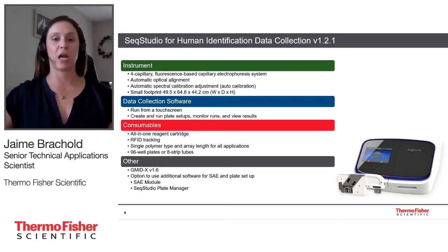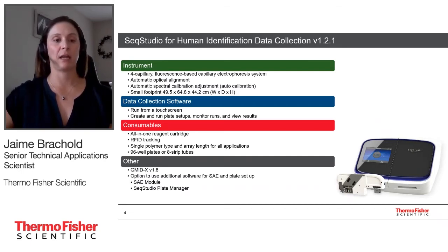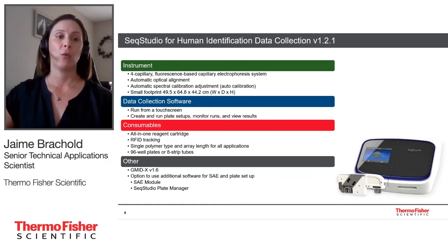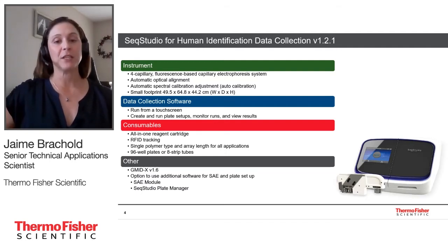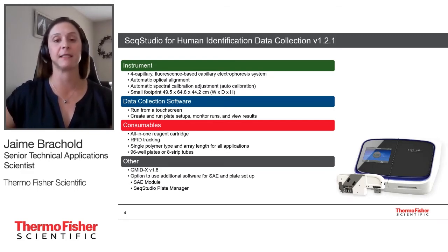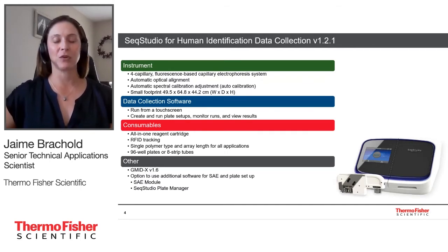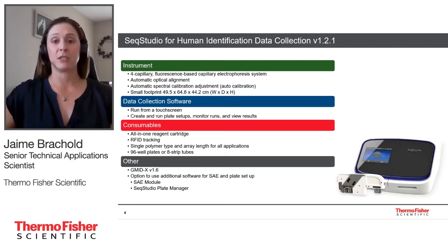There is also some optional adjunct software — an SAE module to set up different users and permissions, and a SeqStudio plate manager to help set up plate maps that can be imported into the instrument. The SeqStudio uses a single polymer type: POP1, used for sequencing, general fragment analysis, and STR fragment analysis, so you don't have to worry about changing polymer when running different applications. It is a 28-centimeter capillary array.